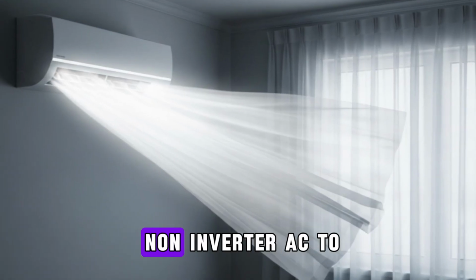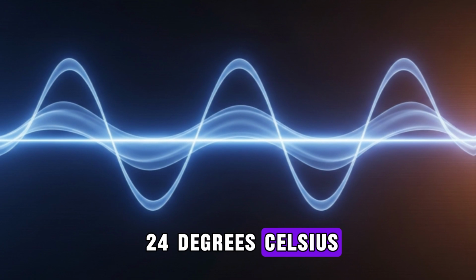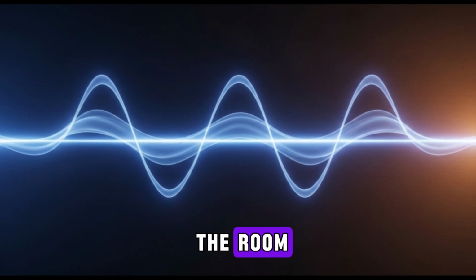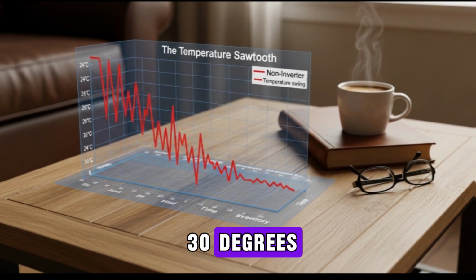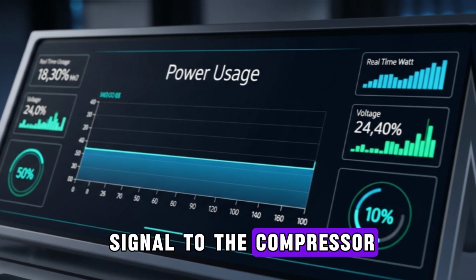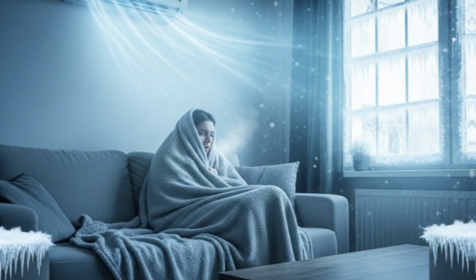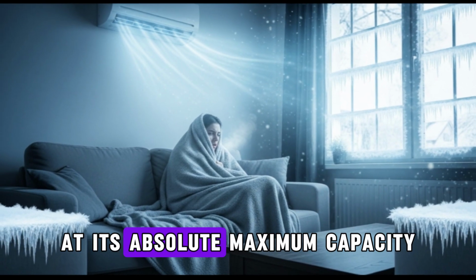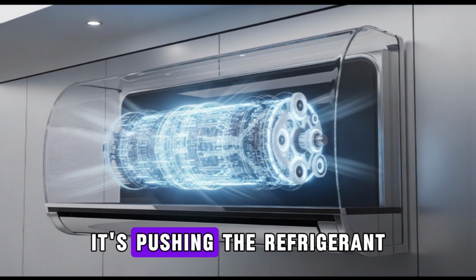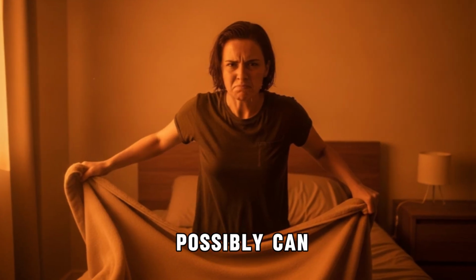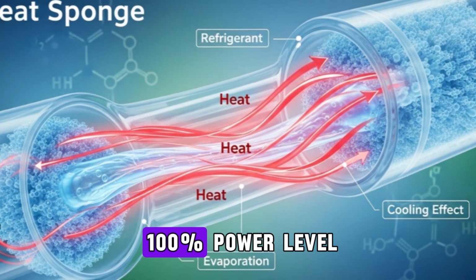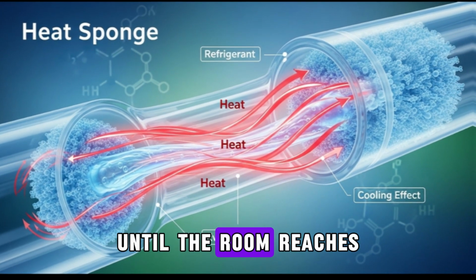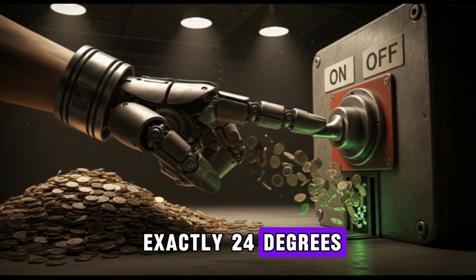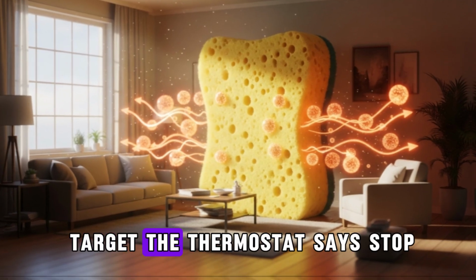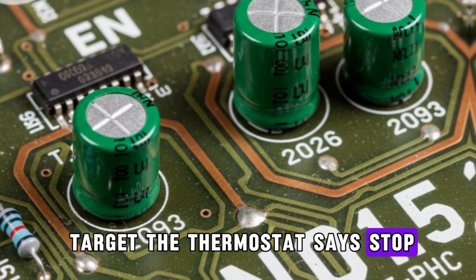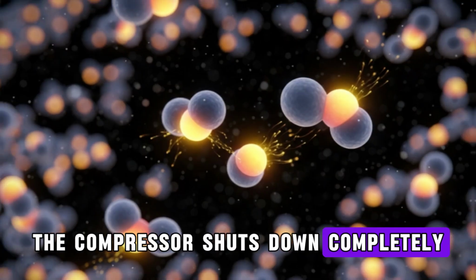When you set your non-inverter AC to 24 degrees Celsius, the machine looks at the room. If the room is 30 degrees, the thermostat sends a signal to the compressor, GO. The compressor kicks on at its absolute maximum capacity. It's pushing the refrigerant as hard as it possibly can. It stays at that 100% power level until the room reaches exactly 24 degrees. Once it hits that target, the thermostat says, stop. The compressor shuts down completely.